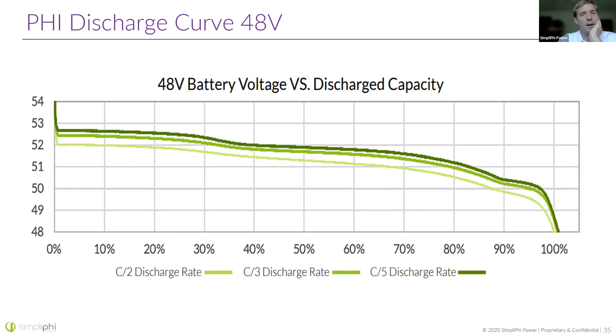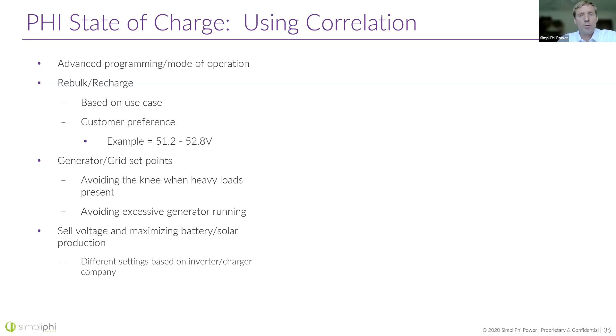You can have a generator set point so that when the battery drops to 20% state of charge remaining, meaning 80% discharged, the generator kicks on. That can support your loads or charge up your battery. Some customers want to sell their energy back to the grid, while others want to keep the battery topped off for emergencies. Have that conversation with your customers.